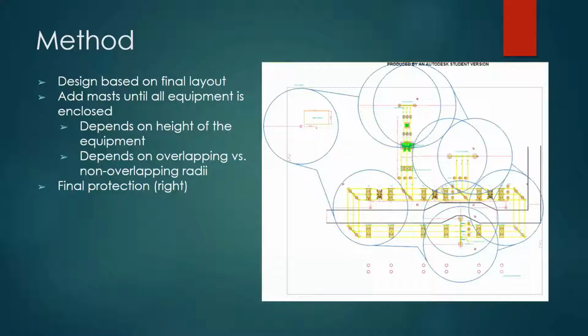So our design of the lightning protection was based on the final layout of our substation. We originally had 6 masts already in the substation, and so we just needed to keep adding masts until all the equipment was enclosed. So the protection that each mast provides depends on the height of the equipment it's protecting and whether it has an overlapping versus non-overlapping radii of protection. And IEEE determined that non-overlapping radii offered more protection, as lightning was more likely to hit that higher object than it was to hit the equipment below it. And so you can see our final protection there on the right.